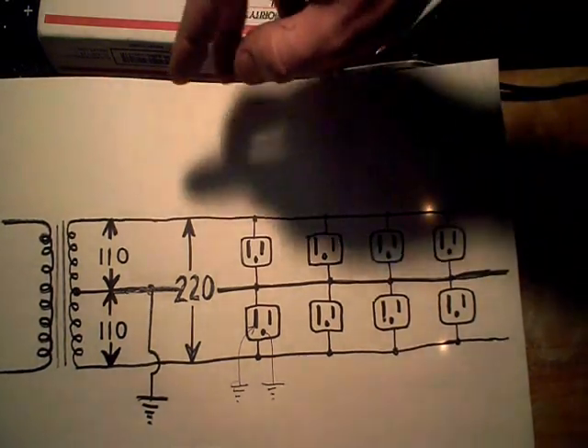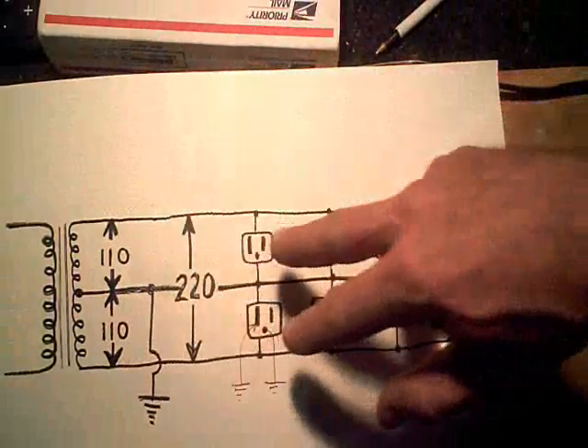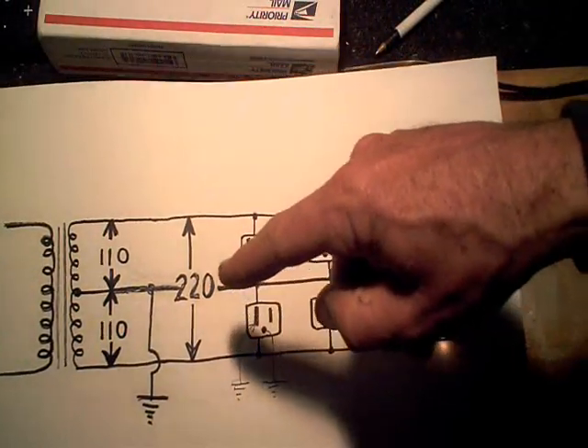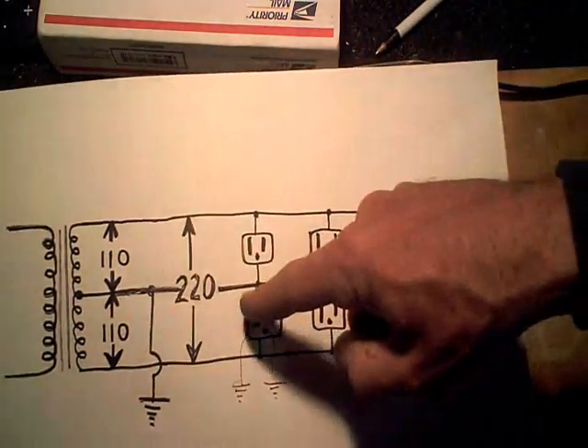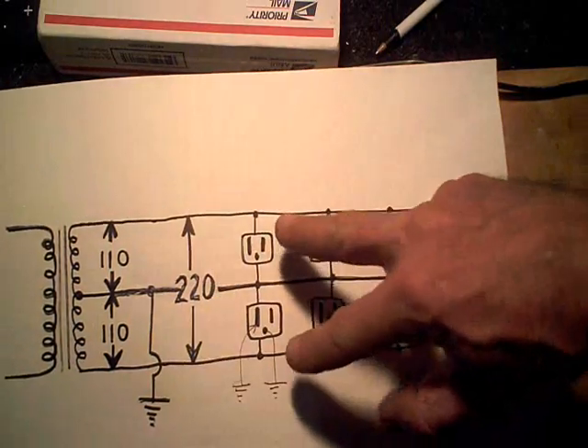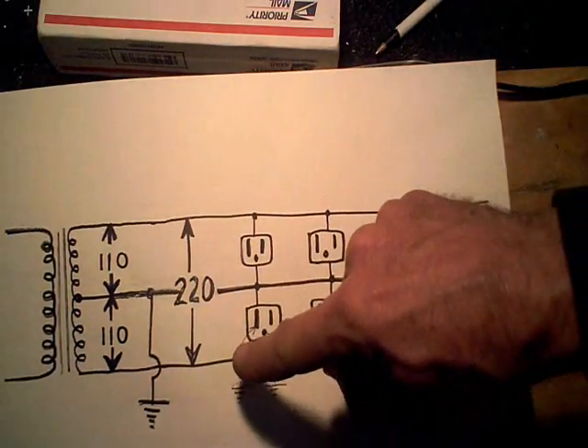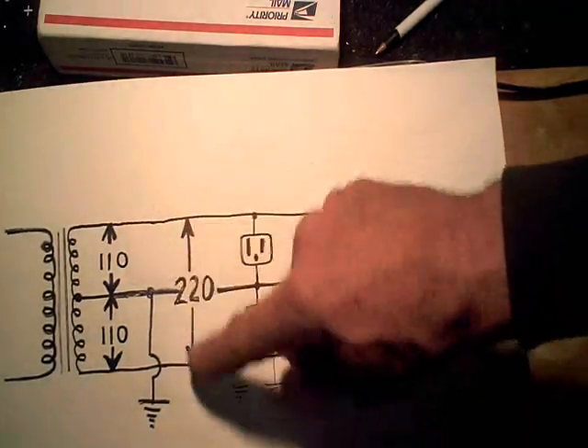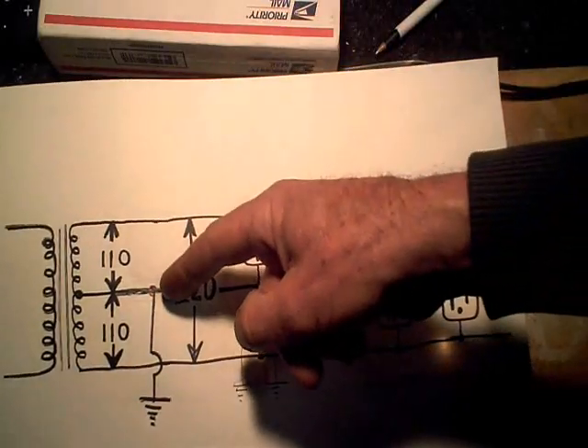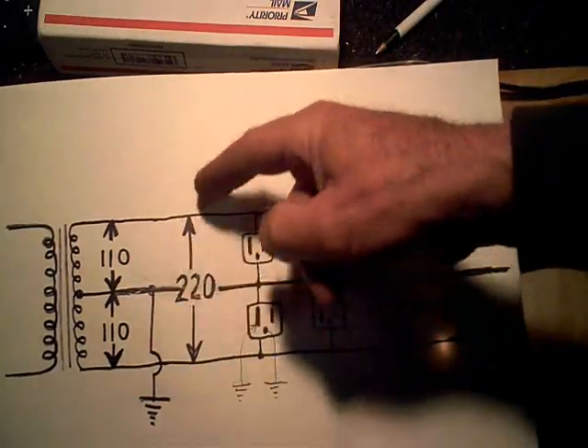Basically, if you look at the wires that go into your house, you've got three wires coming off your main pole transformer. You've got your neutral wire and then you've got your two outer legs. So your 220 is usually between the two outer legs here, and your 110 comes from the center to one of the outer legs.